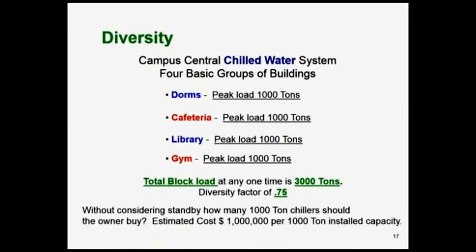Let's look at a simple concept called diversity. If you're going to balance a system, you had best understand this, or how will you balance it? It's a real simple concept. Let's say we've got a central chilled water plant with a dorm with a 1,000-ton load, a cafeteria with 1,000 tons, a library with 1,000 tons, and a gym. If you add up the individual loads, it's 4,000 tons. But if you run a block load and look at all those 4 buildings at any one time, the peak block load of those 4 buildings is 3,000 tons. By my definition, that's a diversity factor of 0.75.